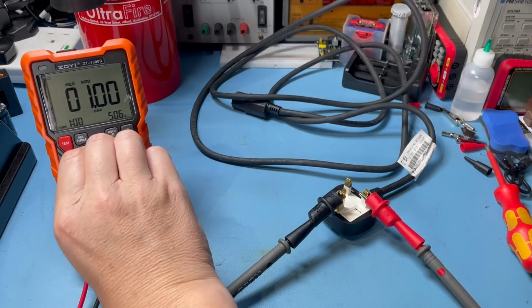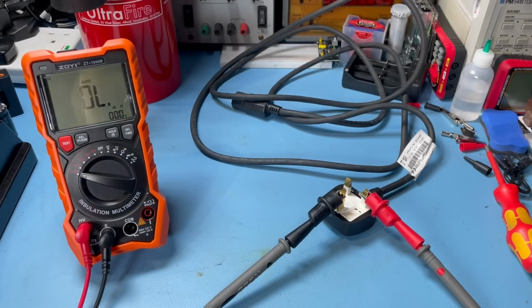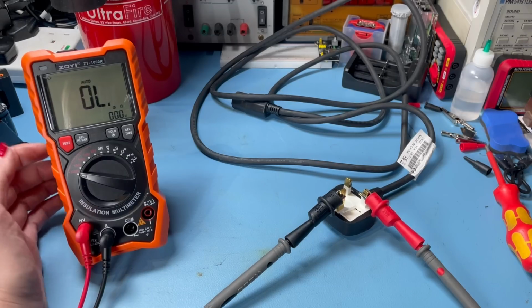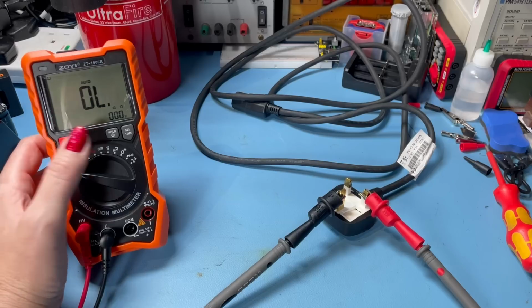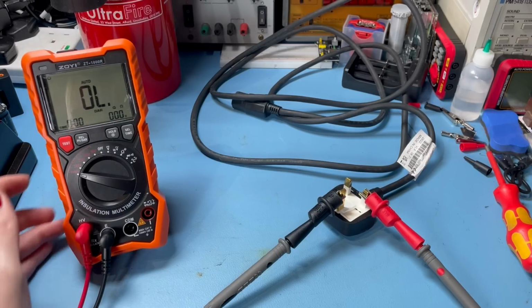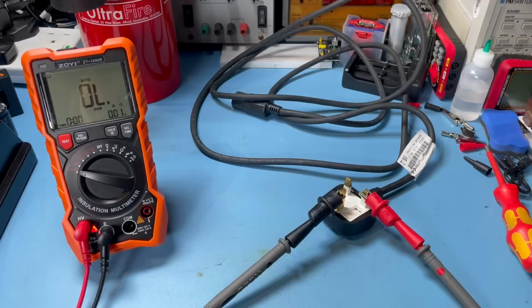Now, just to show off the full capability of the Zoyi, I'm going to test this cable now at 1000 volts. It's not something that you would ever do, and I don't recommend doing it. It's well above the testing that you need to do on these kind of cables. 500 volts is absolutely fine. But as I always say, it wouldn't be a thorough test if I didn't test it thoroughly. So let's go, and you can see the Zoyi is indeed putting out 1011 volts.